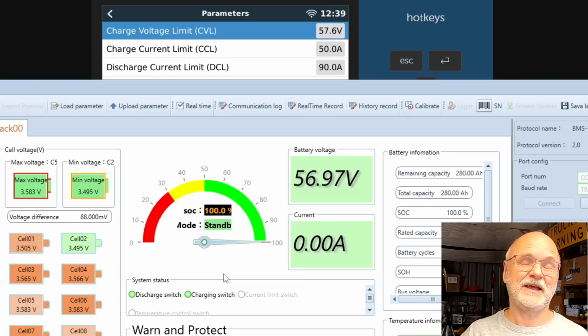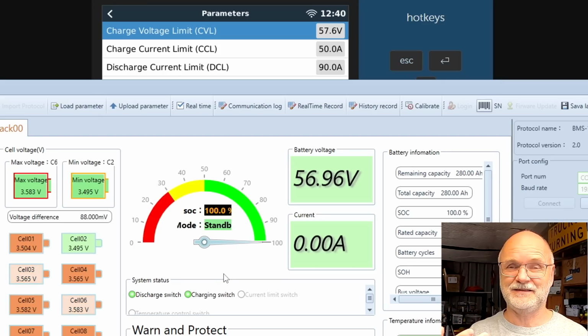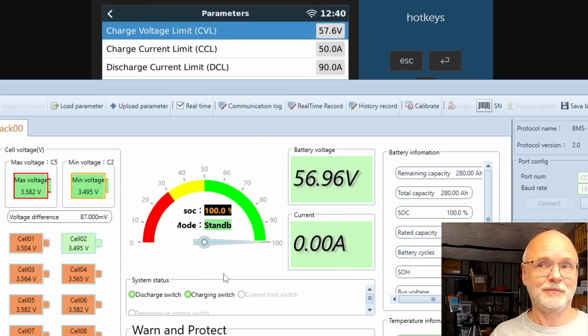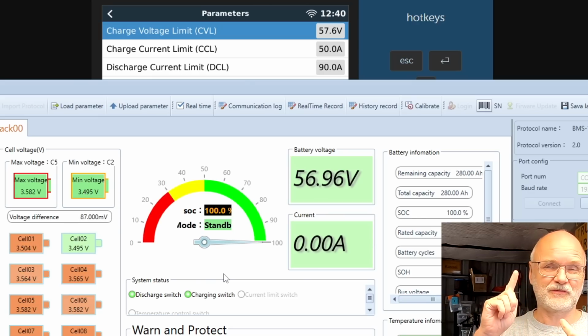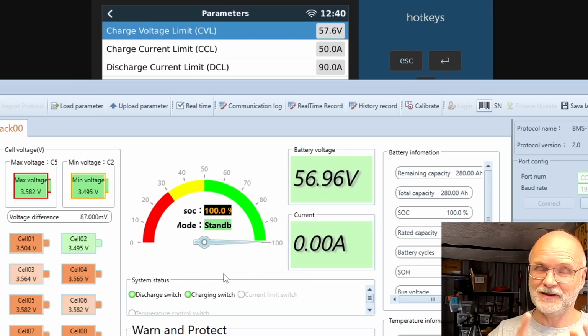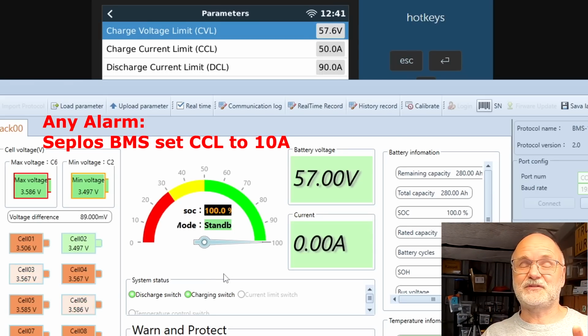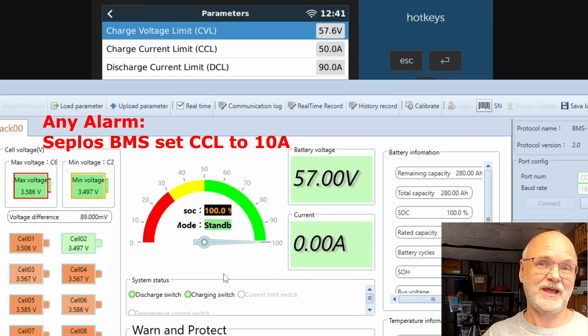And all these alarms or protections usually have one thing in common: they reduce the charging current into the battery. This is a very unique feature with the Seplos BMSs, which some people like and some don't. I don't like it, and I'll talk about it in a second. As soon as you hit an alarm, over current, over temperature, over voltage, any high voltage alarm, any of these alarms cause the BMS to tell the charger to slow down to 10 amps.